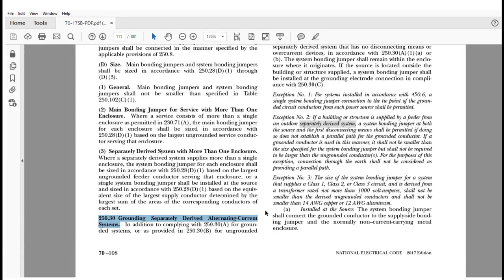All right, in the previous code, that's what you had to do. In order to establish a grounding electrode system for this separately derived system, the 2014 code said that you had to go to the nearest of either the metal water piping ground, as identified in 250.52(A)(1), or to a structural metal frame of the building or structure, described in 250.52(A)(2). They had to be utilized, and they had to be the nearest one, and that was what you chose. Nearest, as near as practical, is preferably in the same area.